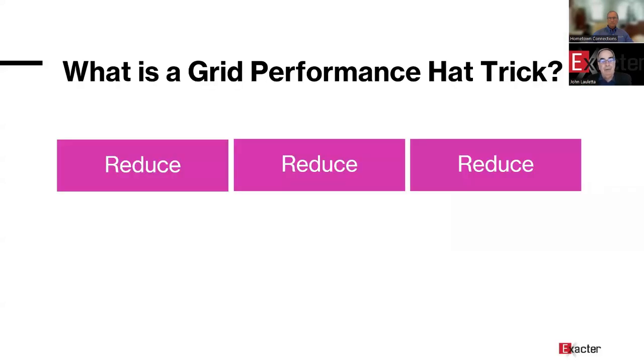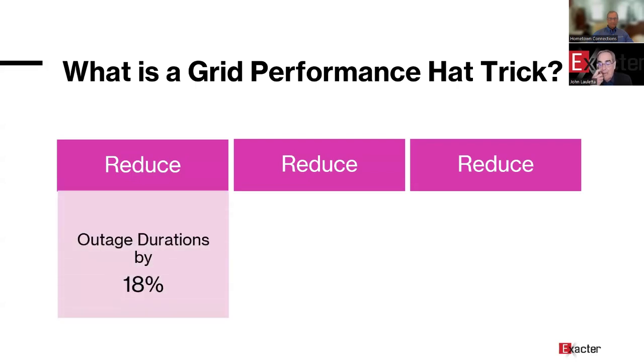So what can you get from this? Well, this is aggregated data from our 18 years of history of running predictive maintenance programs in the United States and 5 other countries. The first thing is you can reduce the outage duration by up to 18%. What does that mean? That means your customers are going to have, if they experience an outage, a shorter period of outage. Why? Because you're going to know before you go out to seek the problem what could be the problem based upon the condition measurements that have already been taken.